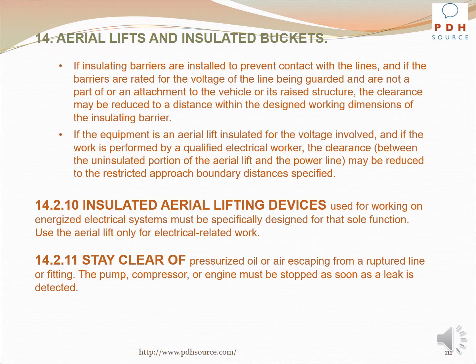If insulating barriers are installed to prevent contact with the lines, and if the barriers are rated for the voltage of the line being guarded and are not a part of or an attachment to the vehicle or its raised structure, the clearance may be reduced to a distance within the designed working dimensions of the insulating barrier. If the equipment is an aerial lift insulated for the voltage involved, and if the work is performed by a qualified electrical worker, the clearance between the uninsulated portion of the aerial lift and the power line may be reduced to the restricted approach boundary distances specified.